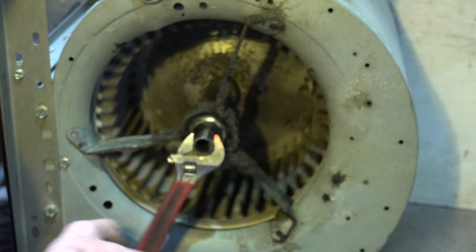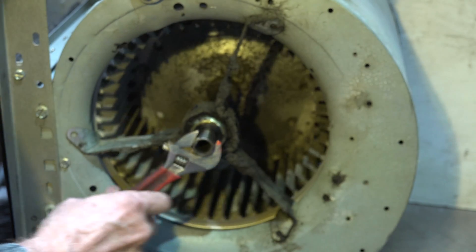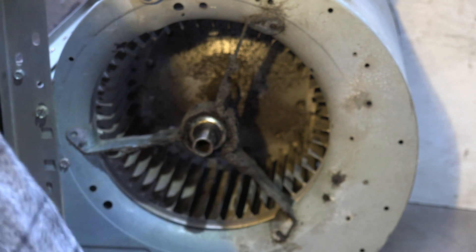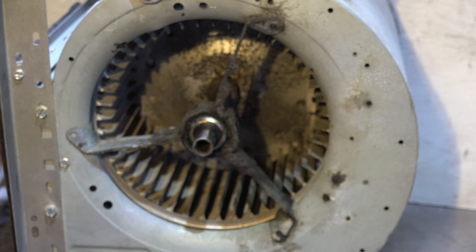The bearing has actually seized, and what it's going to do is run away, and then that bad rubber sleeve is going to wear out and everything goes to heck. So that's what the problem was — the bearing has failed. You have to watch this pretty close when you're doing service on these things; you may not notice it. Anyway, that's it on that one.